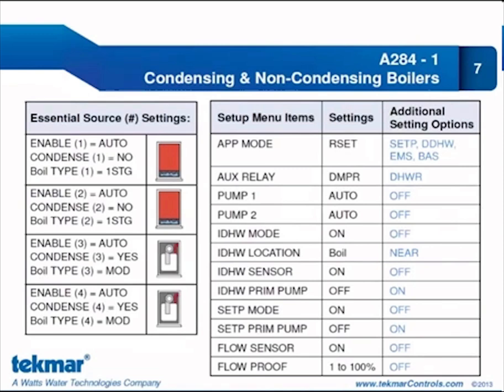Do we need the primary pump to operate for indirect domestic hot water? Well, in this case, the IDHW is piped in parallel. So no, we do not need that primary pump to operate. We turn it off. Again, similar to IDHW, if we're doing set point, we must turn that mode to on, and then we specify, do we need the primary pump to operate?